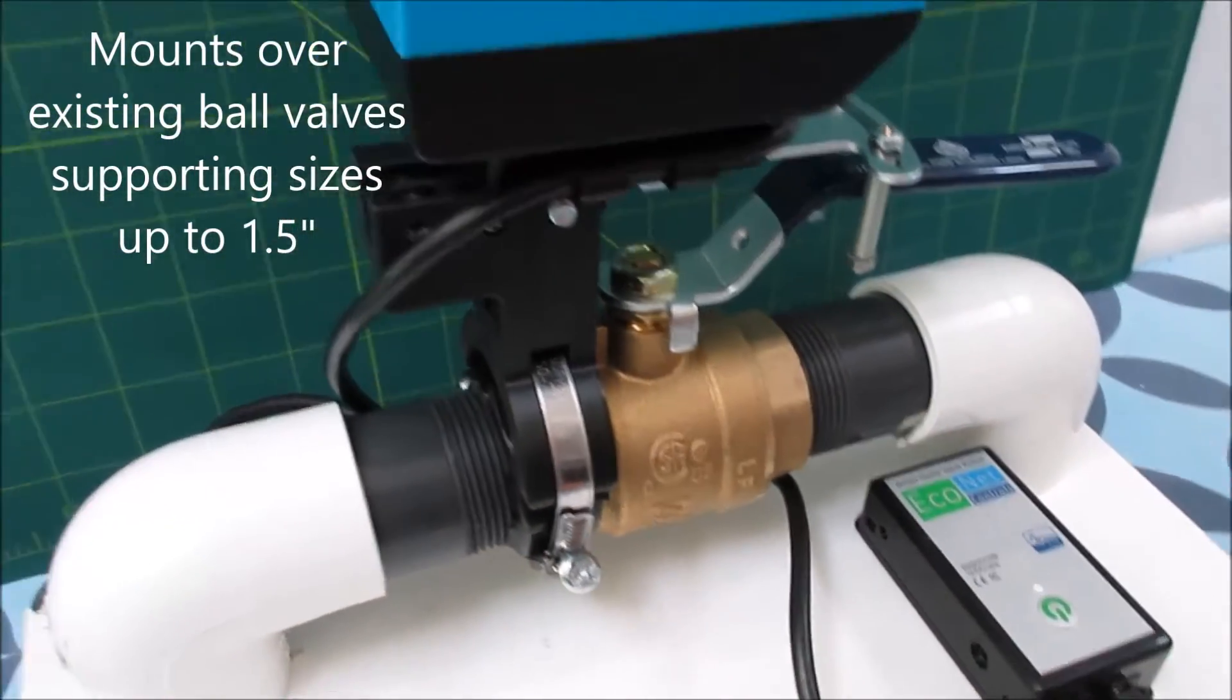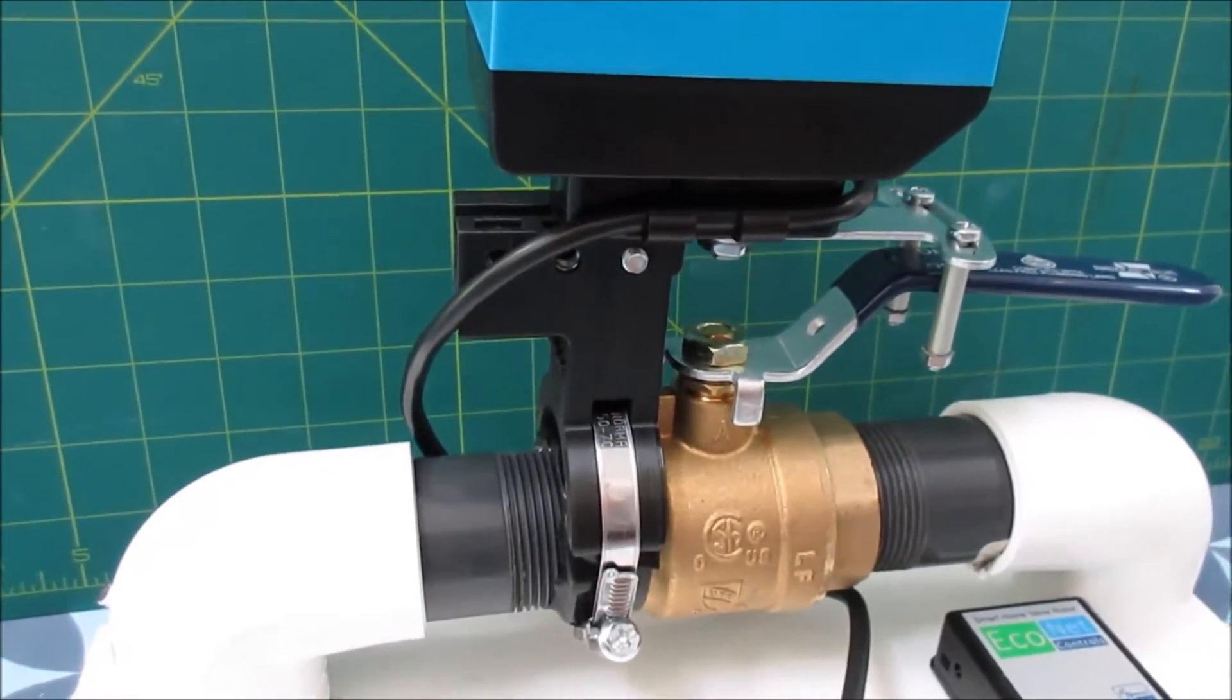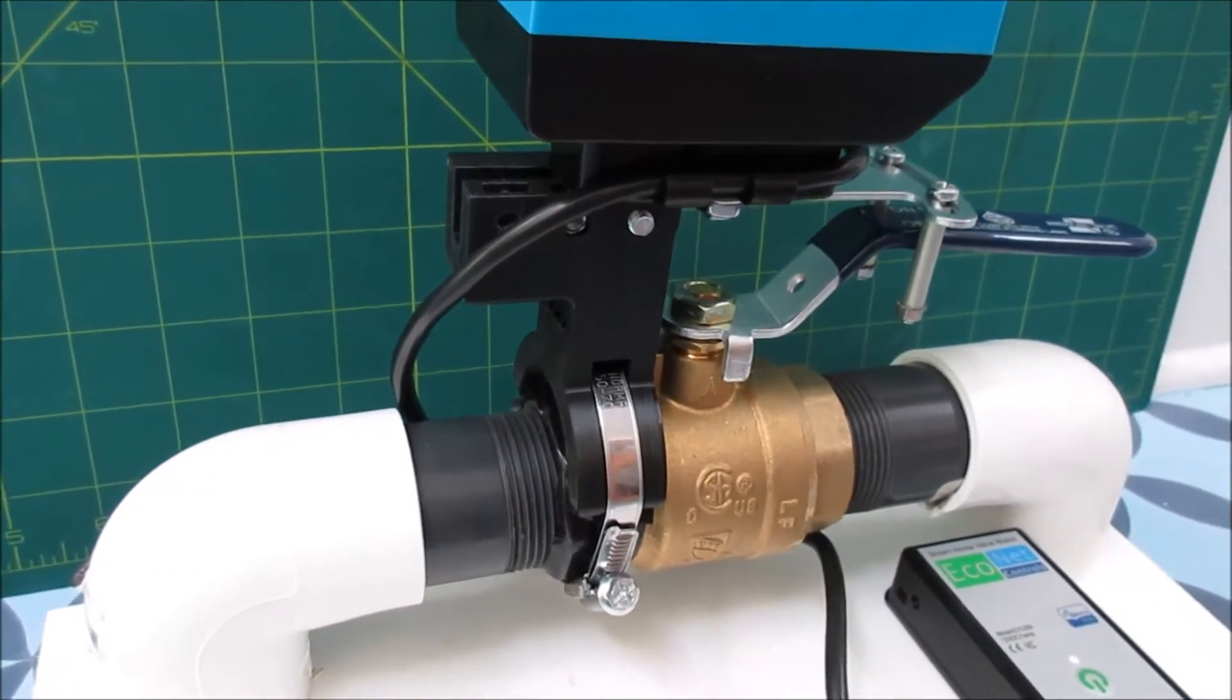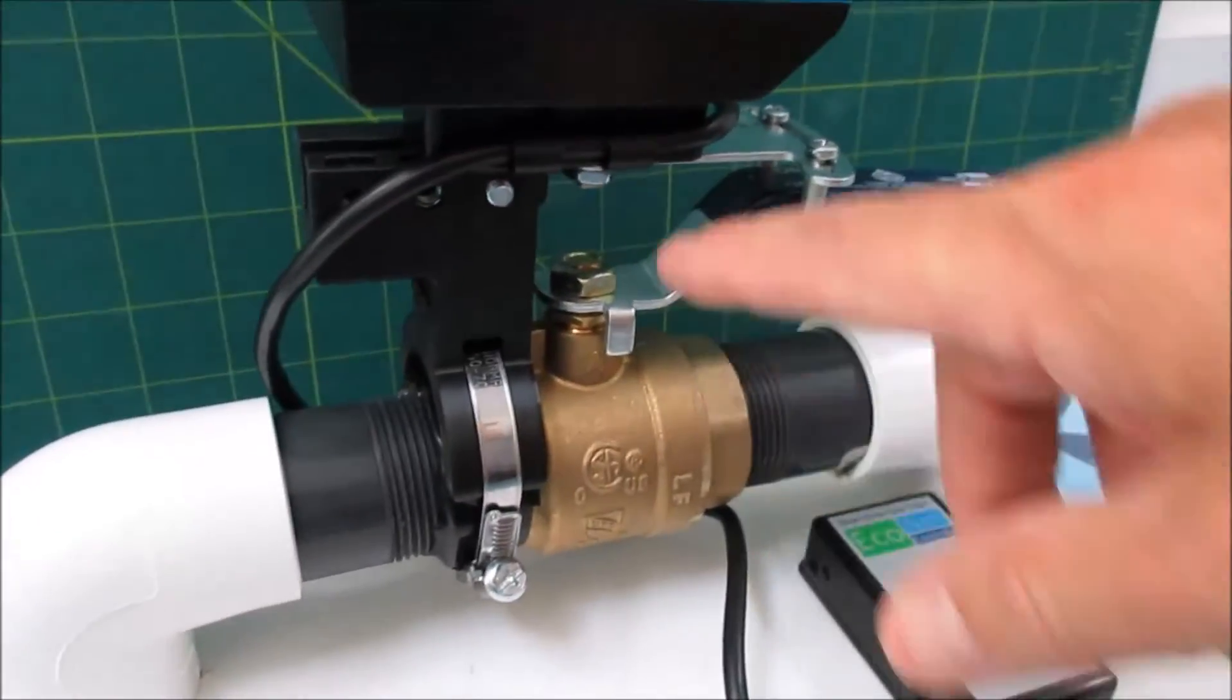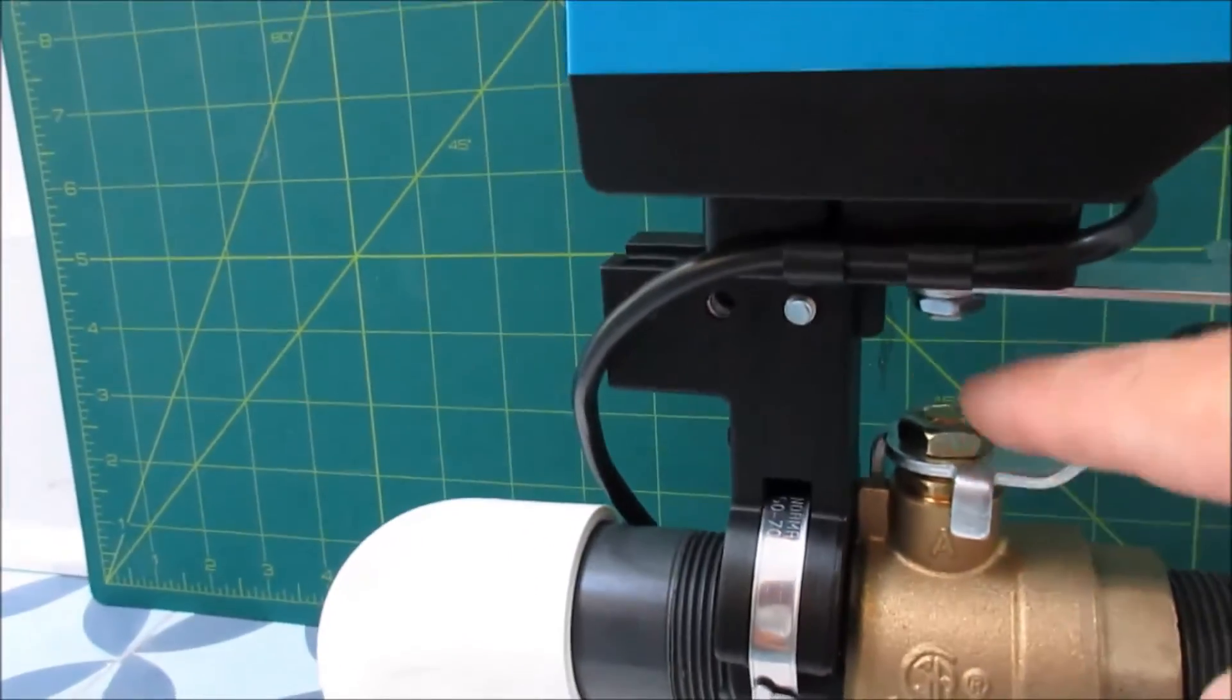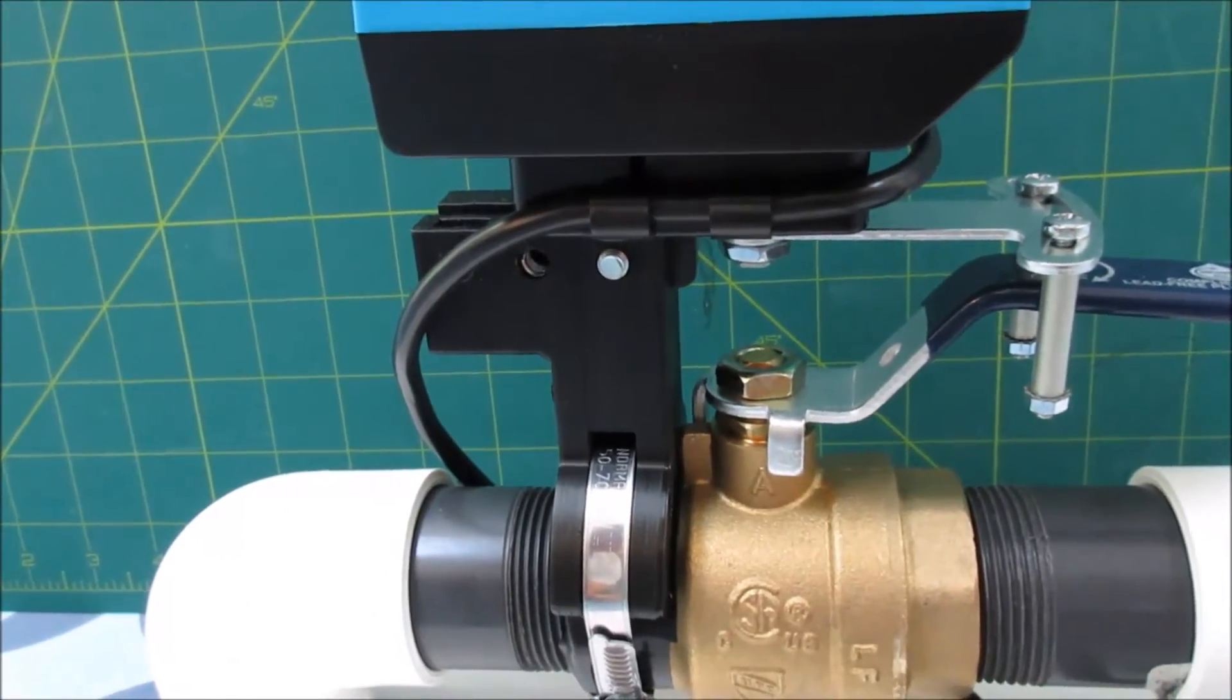This bracket is specifically the extra large designed for one and a quarter and one and a half inch ball valves. In this case we have the flat side here but you could have the L side there depending on the valve type to make sure it's easier to line up the pivot points. And it's important to line up the pivot points to make sure the stroke is most efficient.